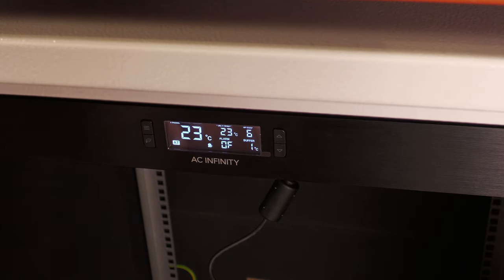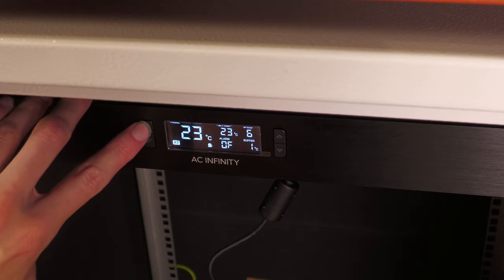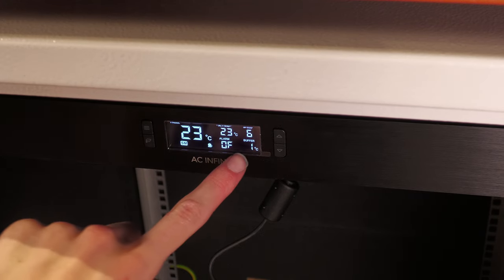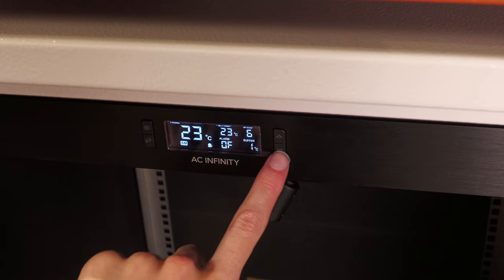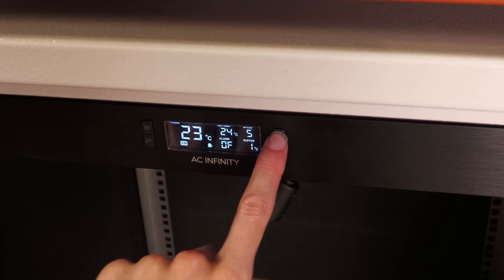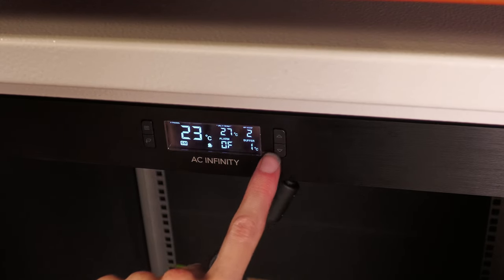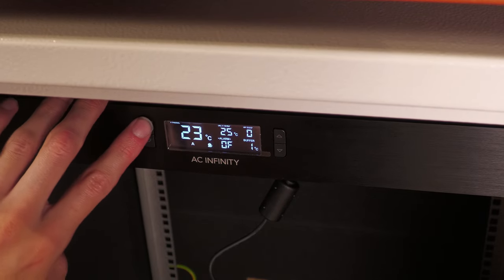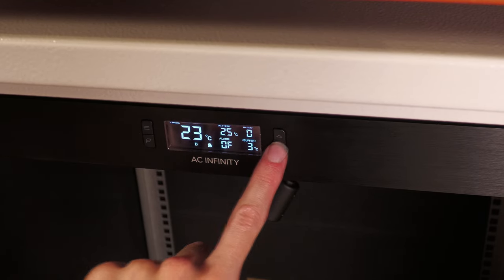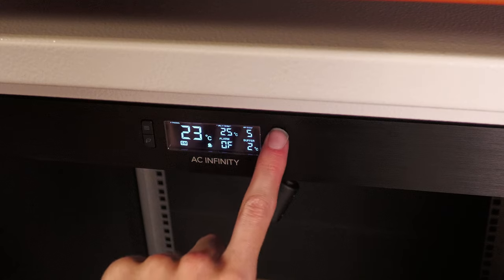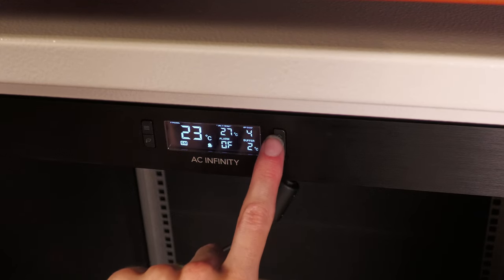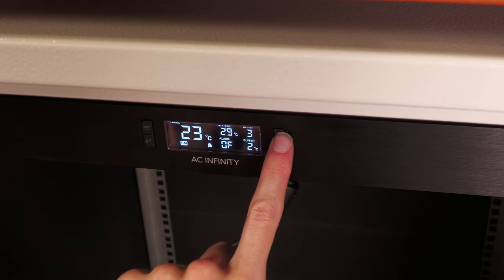So with this, if the temperature fluctuates by 1 degree, that can turn the fan on and off. If you set that to 4, the temperature would have to increase by 4 degrees before the fans turn on, and then decrease by 4 degrees for the fans to turn off. Under smart mode, this defines how quickly the speed changes. So with it set to 1 degree, you can see every time I move the set temperature up by 1, the fan speed drops by 1. On the other hand, if I set the buffer to 2 and go back to smart mode, every time I increase the set temperature by 2 degrees, the fan speed changes by 1.